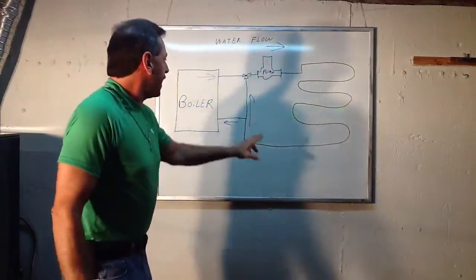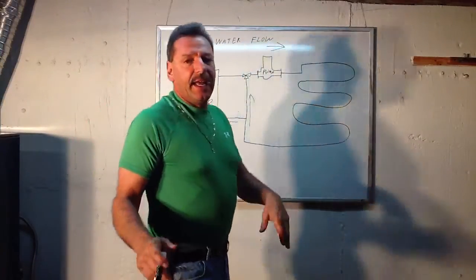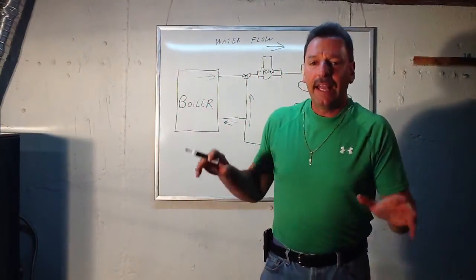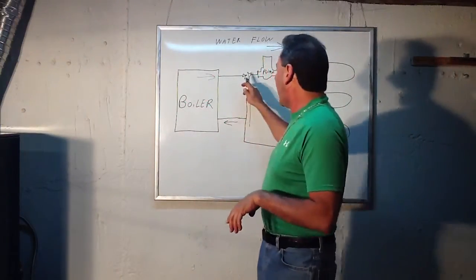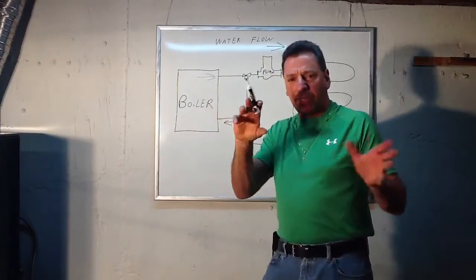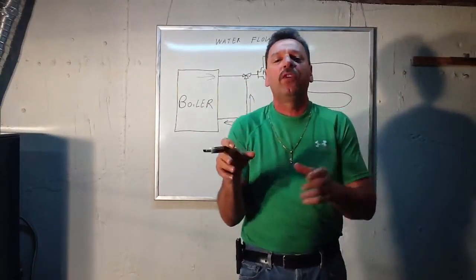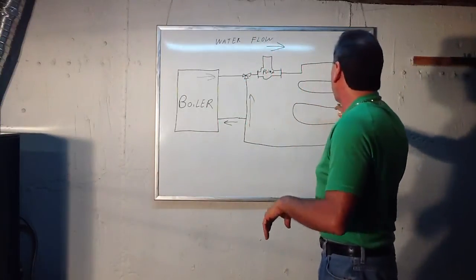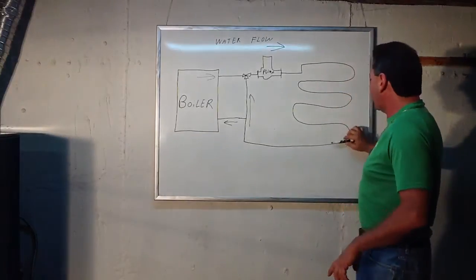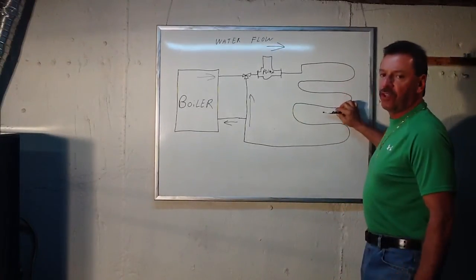So by having that mixing valve on there, it keeps the floor from getting too hot. It maintains the temperature, and there's a dial on this mixing valve that lets you put the temperature at 130, 135, 115, 120, whatever you want.